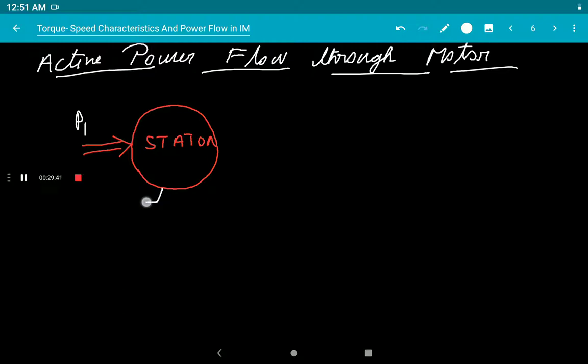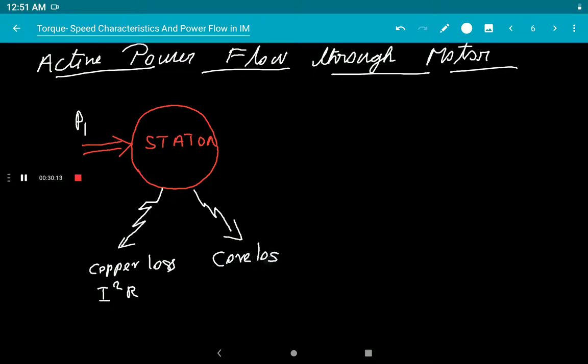What are the stator losses? Look here, there are two losses. One is copper loss, because there are stator windings. So the first loss is copper loss, that is I square R loss. The stator windings have some resistance, so there will be I square R loss, and there will be some core loss, which we have studied in transformers also, that is hysteresis and eddy current losses. Same as in the stator of the induction motor, there will be some core losses. So stator core loss and stator copper loss will be there.